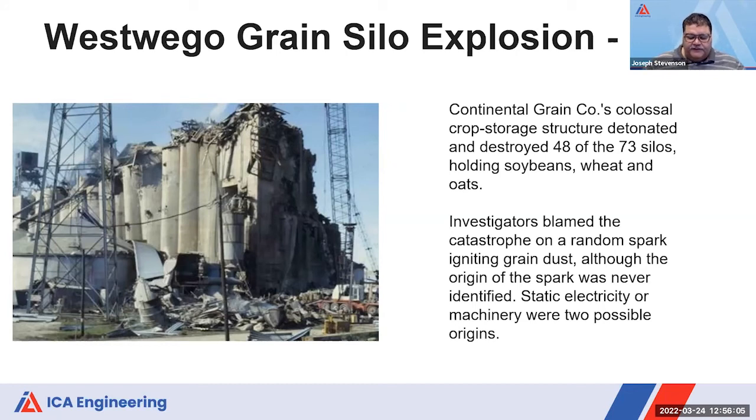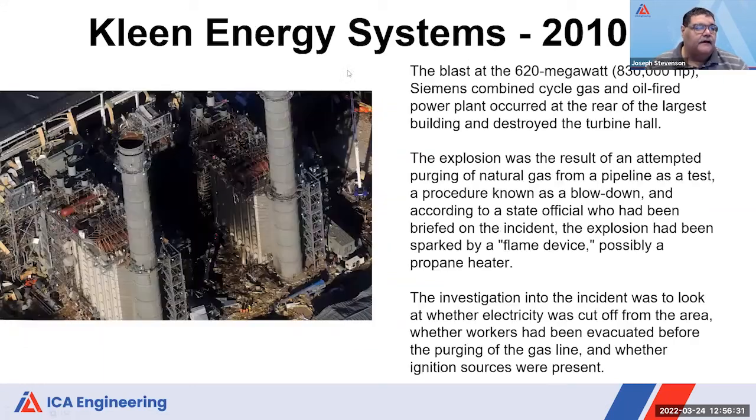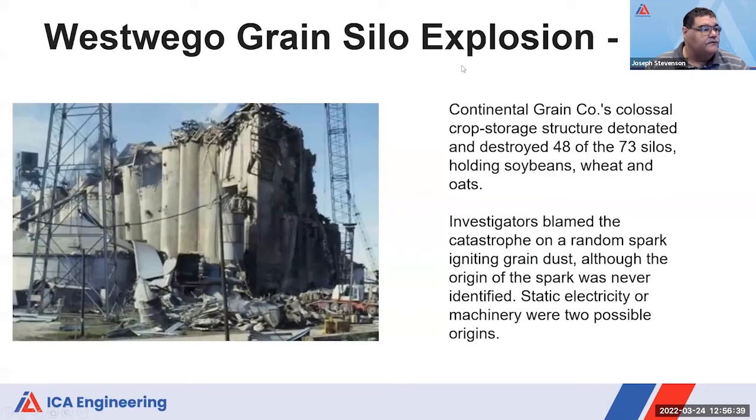Now, just to talk about some applications we've done. And this is great because everybody involved is here. For Dave, we replaced the PLC, and the existing system didn't have a touchscreen, or rather they couldn't use it as a touchscreen because it was behind glass, because it was a Class 1 Div 1 area, and there are very few manufacturers who make Class 1 Div 1 rated screens. So one possibility would have been to get a rather expensive touchscreen, $15,000 to $20,000 installed cost. Instead, we reached out to Ed at XLOC, and we ended up getting an intrinsically safe tablet. You want to talk a little bit about that real quick, Ed, while we've got time?